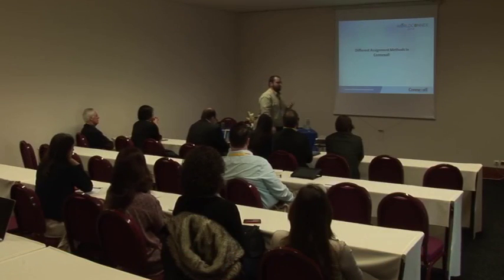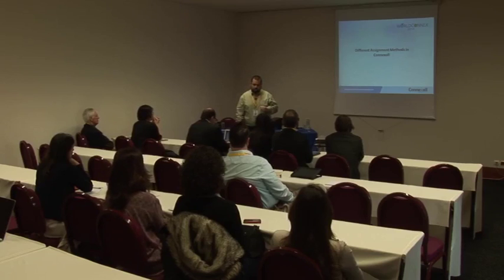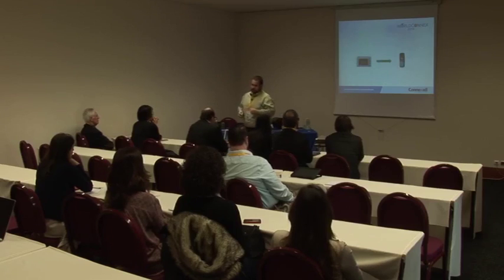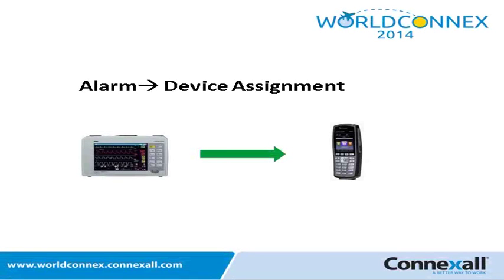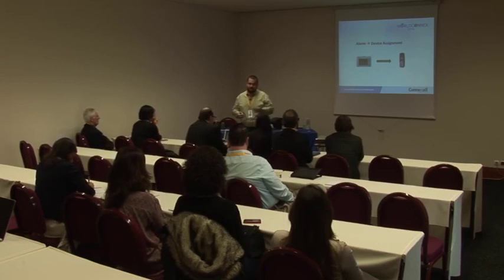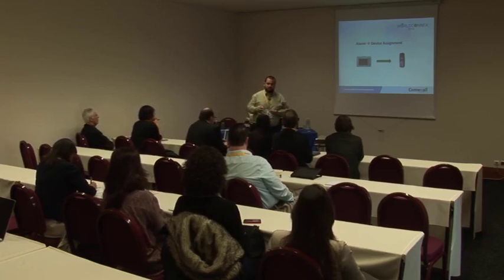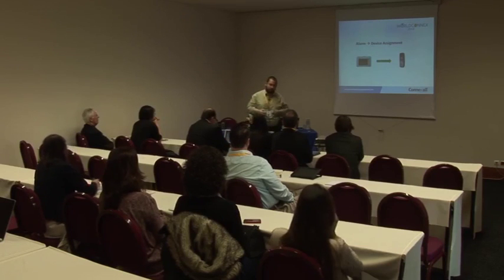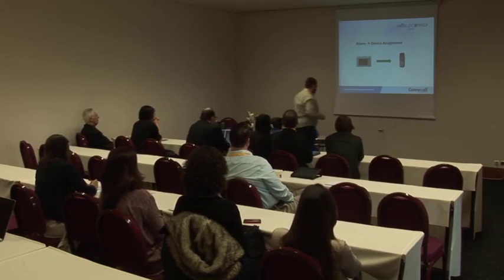We're going to cover two types of assignments out of the 13 or 14 types available. The first is what we call a direct assignment — an alarm-to-device assignment. It's a type of assignment that many of you have used over the years, and it's a simple process of dragging an alarm to a phone. A nurse would come in in the morning, pick up a phone, see what extension she has, select her room and the number of alarms, and drag them to the primary, secondary, or backup level of that phone.